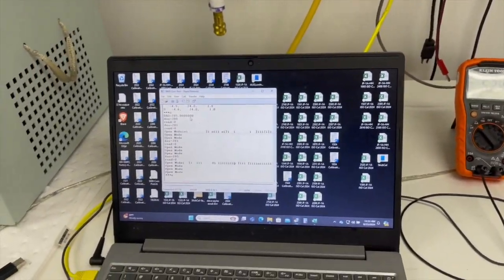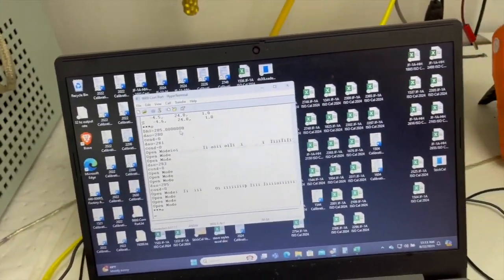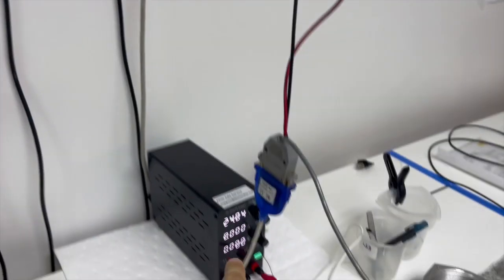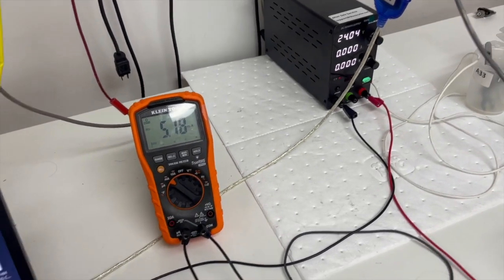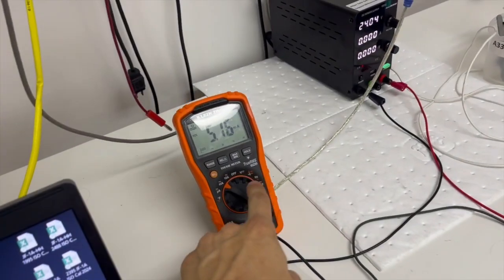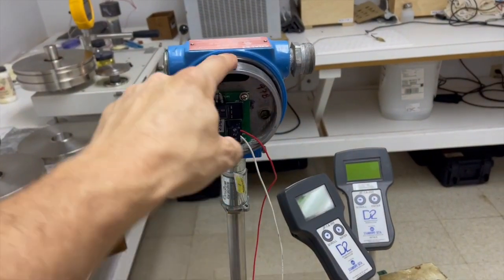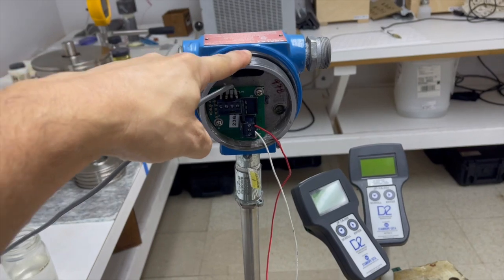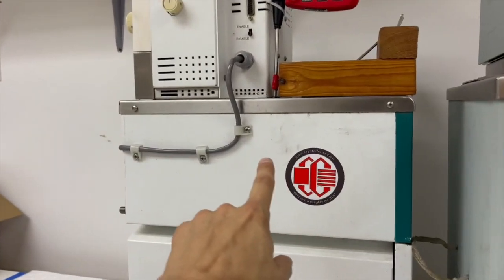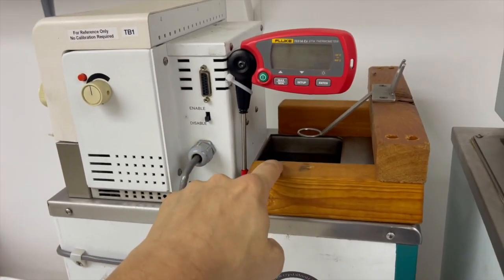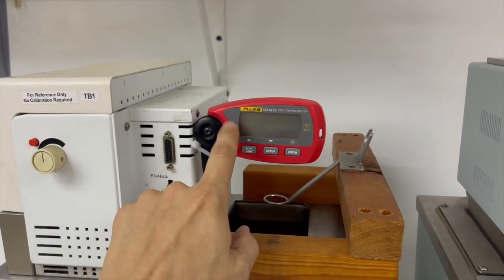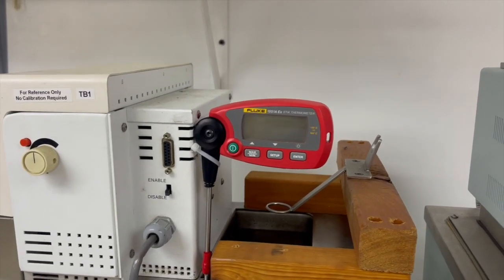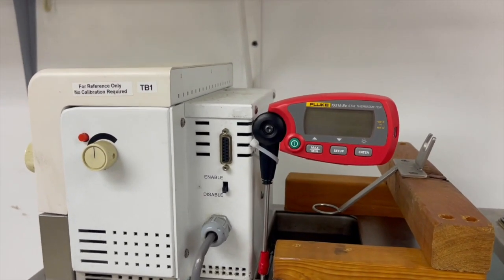You need a computer that has the hyperterminal program on it. You need the 2 power supplies, 24 volt, that we will sell to you. You need one of these, which we'll sell to you as well, which is a calibrated voltage meter. And you need one of these, which is your inline sensor that you're going to be recalibrating. Okay. You also need a temperature bath, and in our temperature bath we use silicone, and we're selling you as part of the kit one of these Fluke temperature gauges that's calibrated, but you'll have to get that recalibrated annually.